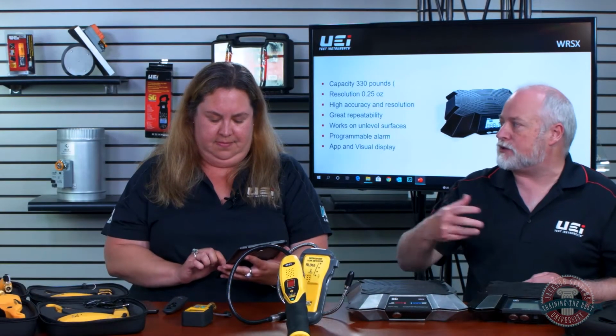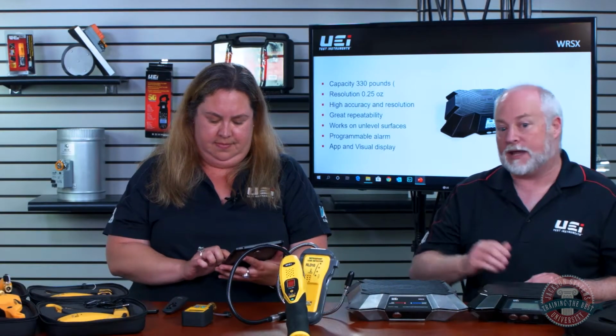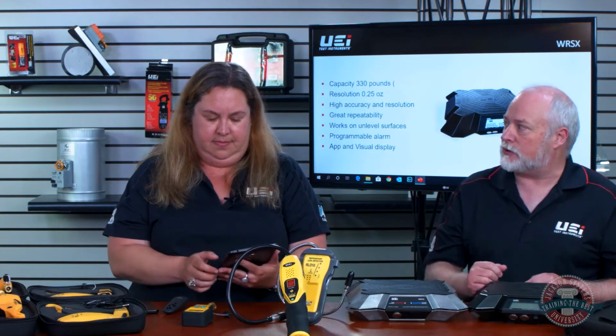So while you're working on charging that system, if you want to set an alarm for how many pounds you want to charge as you're getting close, now we can walk back to your truck or get a tool or something like that and be alerted that, hey, I'm approaching the charge that I want. So you get back to the system and shut that off. It doesn't automatically stop the flow of refrigerant, but it will alert you when you reach that alarm point.